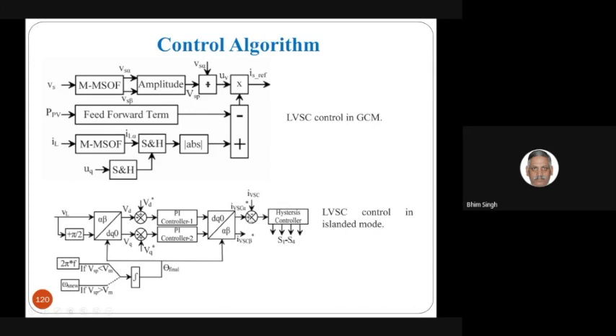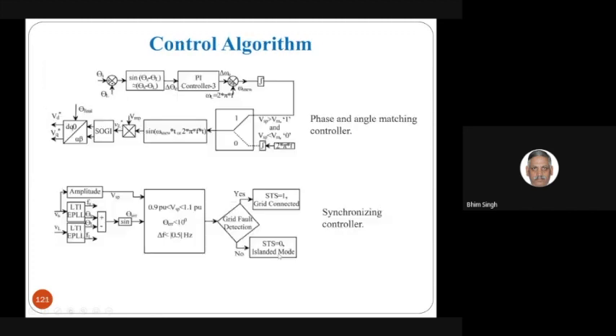For grid synchronization, your voltage and frequency should be within the stipulated range, as well as the angle. After that, you have to synchronize by floating the inverter towards the grid. That's the process for synchronization. The angle of the inverter has to slowly go toward the grid angle, and once they are equal, you can close the switch. These are the conditions for when the grid is acceptable or not. Once the grid is acceptable, only then will the synchronization process start.